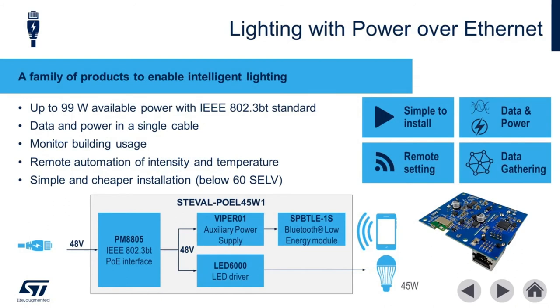Our second implementation of connected smart lighting features a novel approach using Power over Ethernet. The benefits of leveraging IEEE 802.3BT power delivery are numerous. 48 volt DC is considered low voltage and very easy for installation. Data and power are provided on the same cable. A large number of lighting nodes can be controlled remotely using Ethernet, and building data such as occupancy, temperature, and humidity can be collected from remote locations.